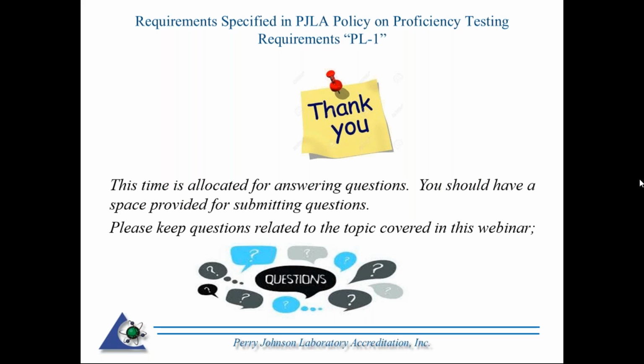I'll throw out an example - if somebody gave me that request for a pH meter or a micrometer, I'm not going to approve it because I know there are plenty of third-party providers out there. So the organization, and I'm the one who approves them for calibration, would need to either go through the third party or do an inter-lab, because even the standard says you have to compare your results to other results outside your organization.